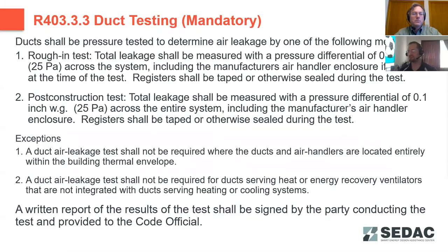Because you want to get the air that you're conditioning throughout the house to prevent having hot spots, cold spots, comfort issues, and to increase the overall efficiency and operation of your HVAC system. Duct pressure testing is mandatory for new construction buildings. You can have that testing done at 2 different times, either a rough-in test before all the drywall and everything is finished in the house, or the post-construction test when the house is just about ready to be occupied. If you're doing the rough-in test, again, both of these tests are at 25 pascals of pressure difference. All the ductwork should be taped off so that it's isolated from the interior of the house, and it creates an enclosed system to do that pressure testing.